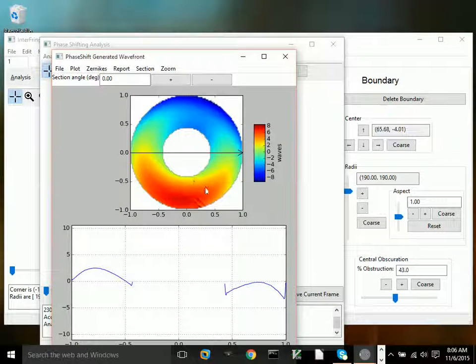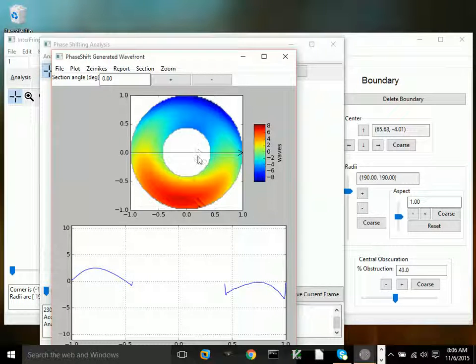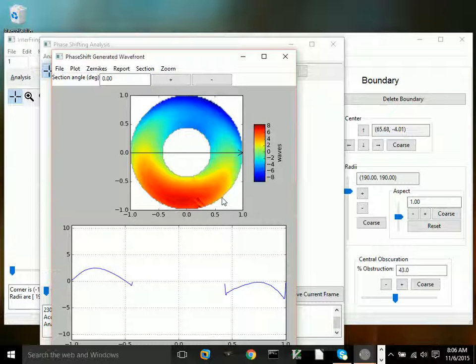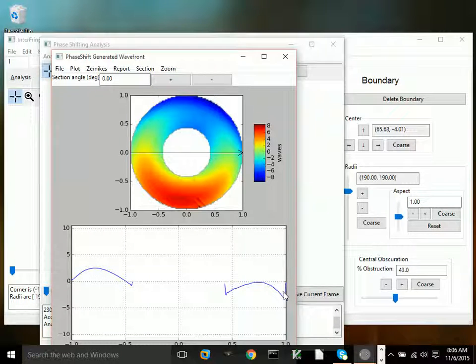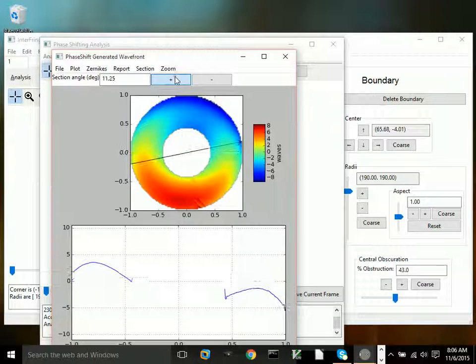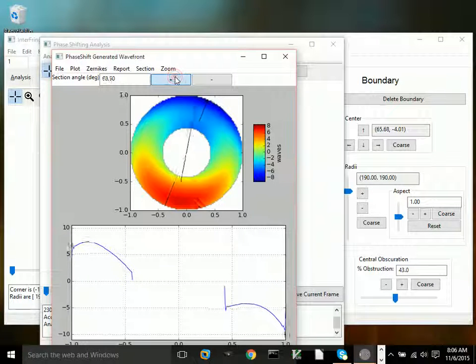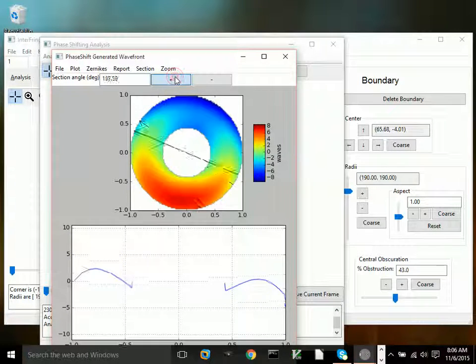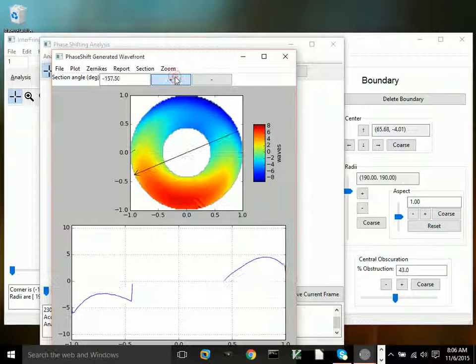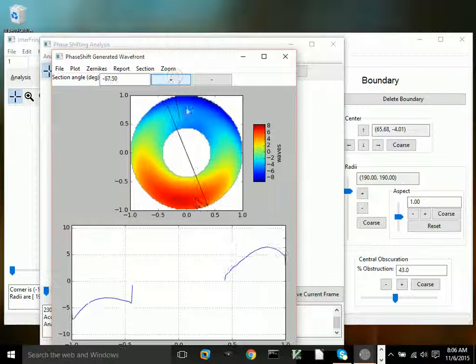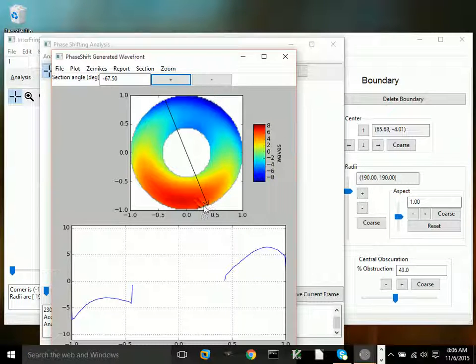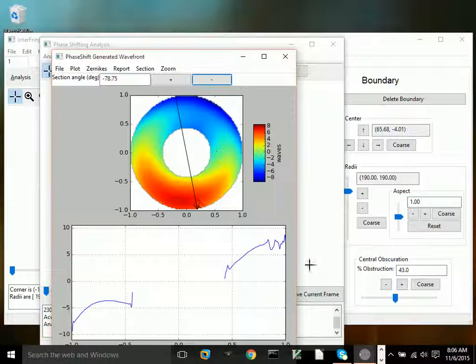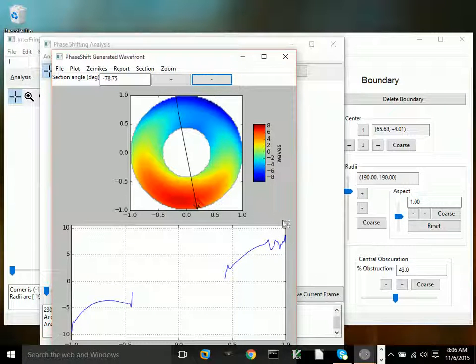The resulting surface is stitched together and provides a fairly continuous and pretty nice looking surface. There are little glitches here on the edges, but very small ones. This feature here is a clip that holds the optic in its test stand. You can see it has a little noise there because it's trying to stitch together something that's varying too rapidly.